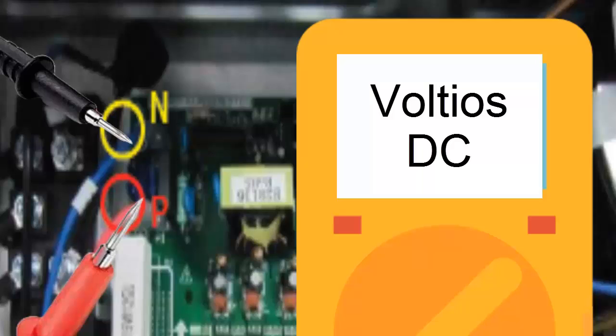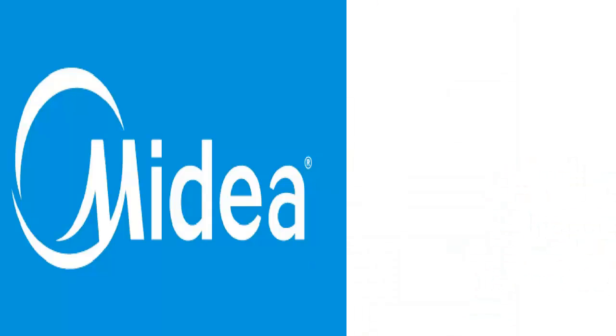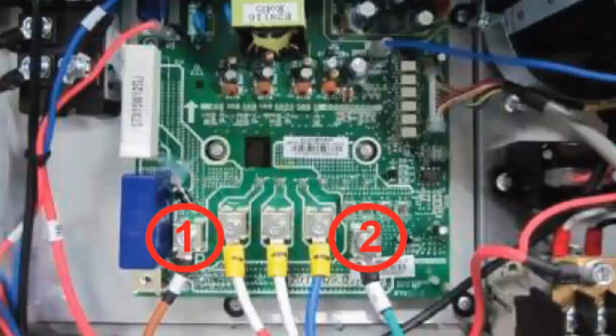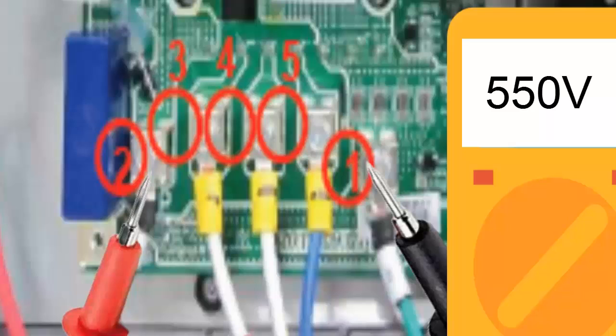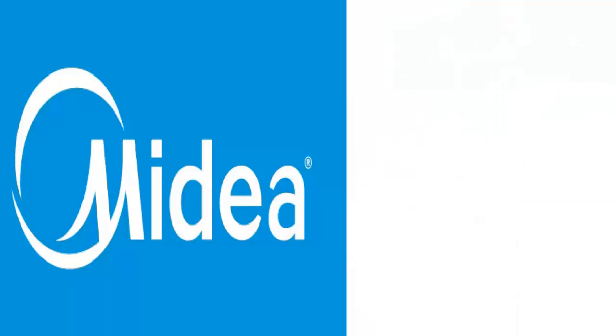4. Measure the voltage between terminals 1 and 2. This value should be between 510 and 580 volts. If these values are not met, the inverter module may be damaged. 5. Check the voltage between the two electrolytic capacitors. The normal value measured in DC voltage should be between 510 and 580 volts.